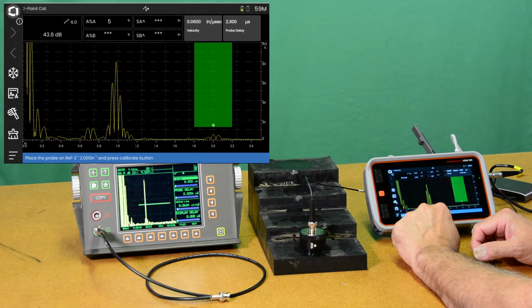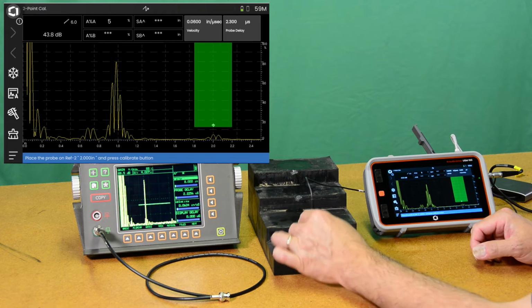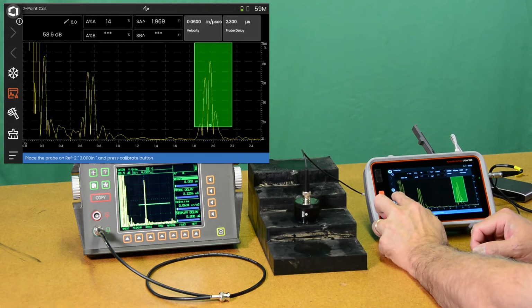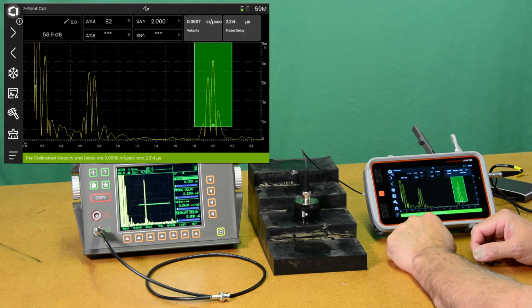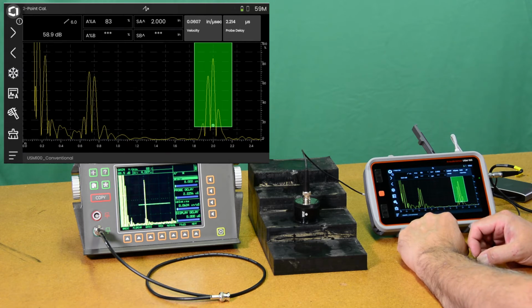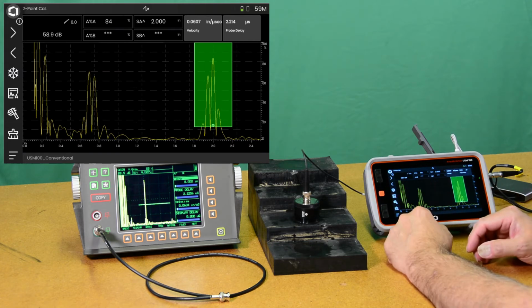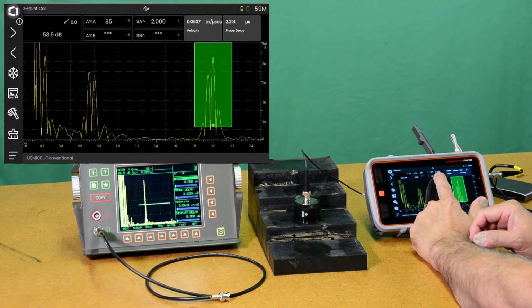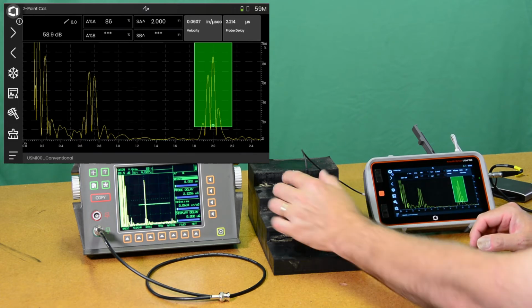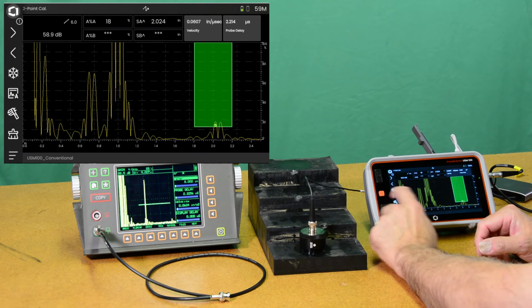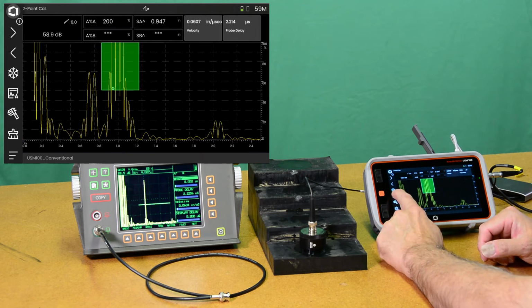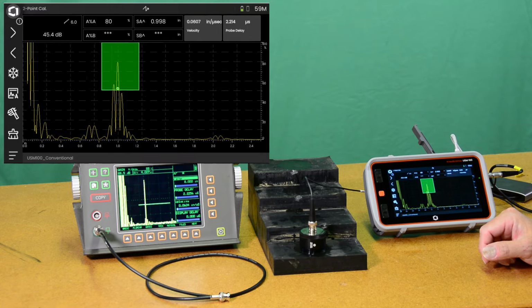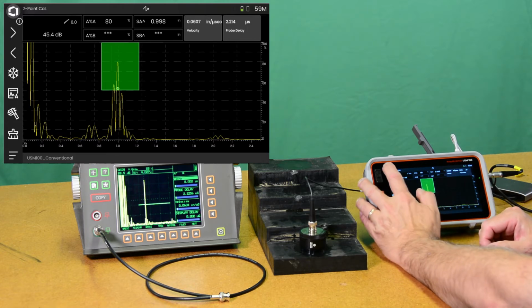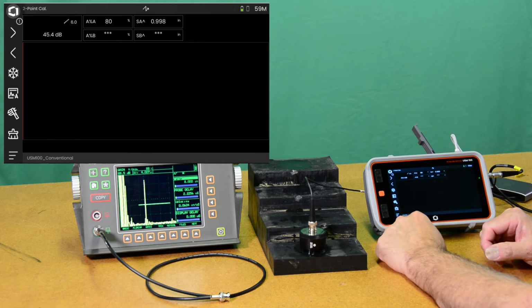Now it's telling me to go to the second step, reference 2, with 2-inch. So I can do that, do auto 80, calibrate, and it comes up with 0.0607 inches per microsecond and 2.214 microseconds of delay. So now we have our delay and velocity calibrated. You can see my gate reading up top here is telling me that I'm measuring 2 inches on that step. We get back here, look at our 1-inch step. Get our gain under control. We're back at 0.998, so effectively 1. Okay, move to the next panel.